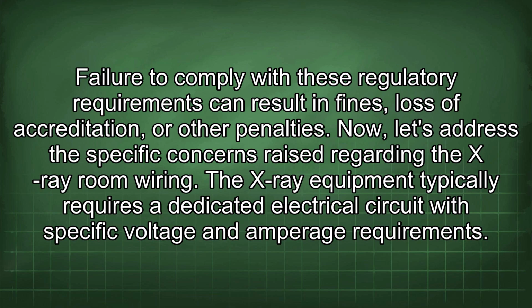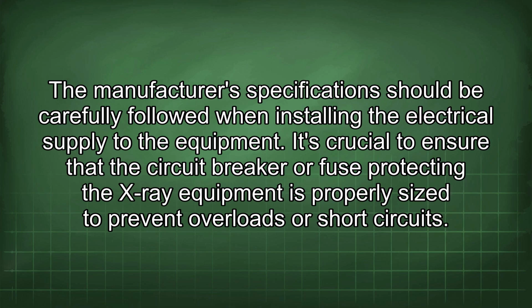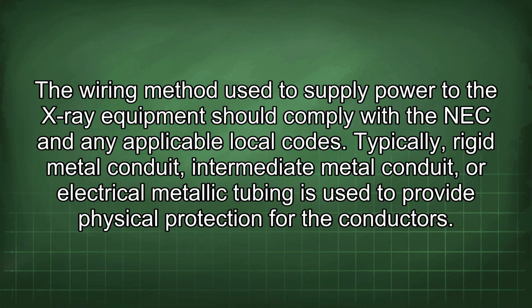The X-ray equipment typically requires a dedicated electrical circuit with specific voltage and amperage requirements. The manufacturer's specifications should be carefully followed when installing the electrical supply to the equipment. It's crucial to ensure that the circuit breaker or fuse protecting the X-ray equipment is properly sized to prevent overloads or short circuits.